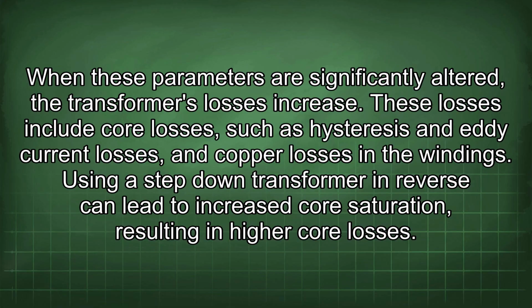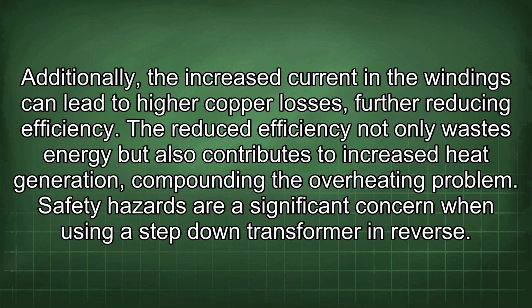These losses include core losses, such as hysteresis and eddy current losses, and copper losses in the windings. Using a step-down transformer in reverse can lead to increased core saturation, resulting in higher core losses. Additionally, the increased current in the windings can lead to higher copper losses, further reducing efficiency. The reduced efficiency not only wastes energy but also contributes to increased heat generation, compounding the overheating problem.